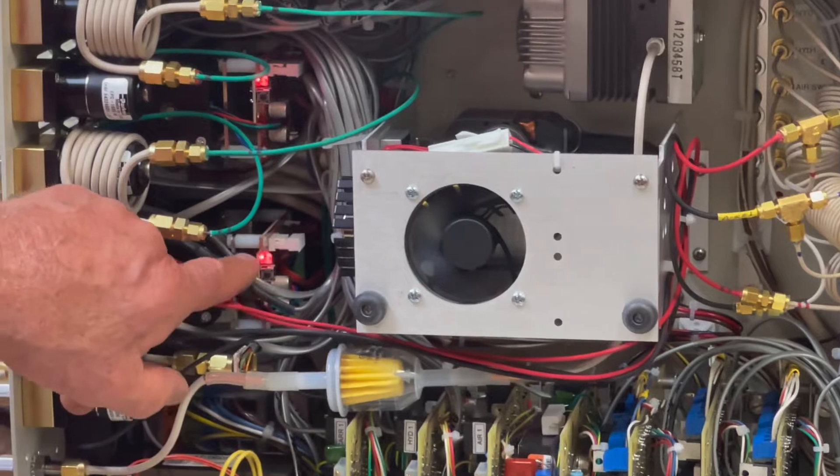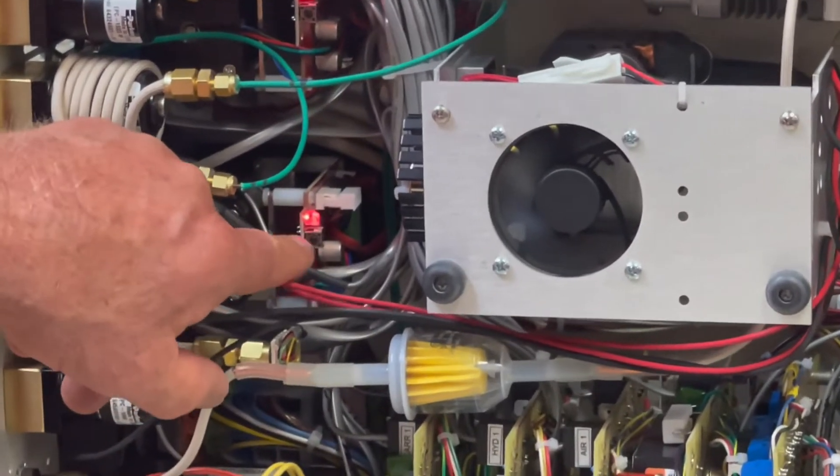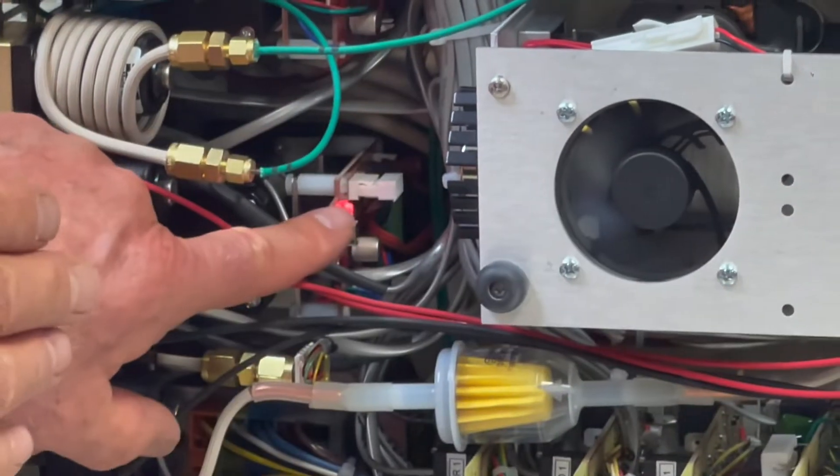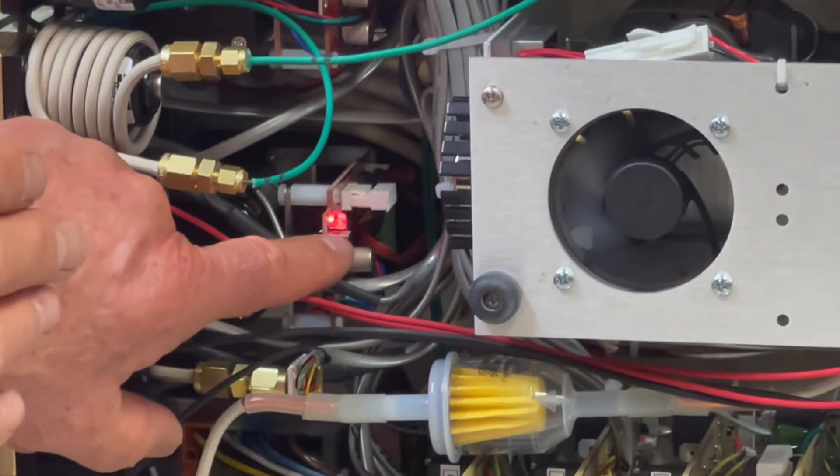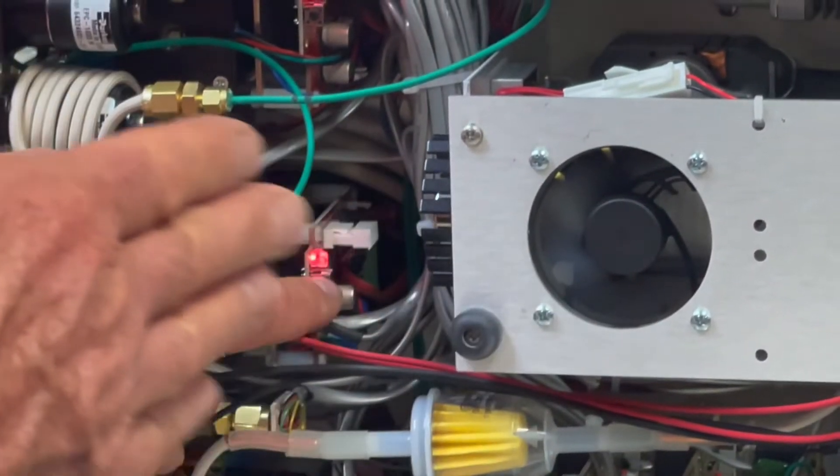Watch what happens, and of course, listen. There's a peculiar sound that happens when the motor is kind of hunting back and forth to feel where it should stop on this end, and feel where it should stop on that end. It does that by kind of sensing where it hits an obstacle.